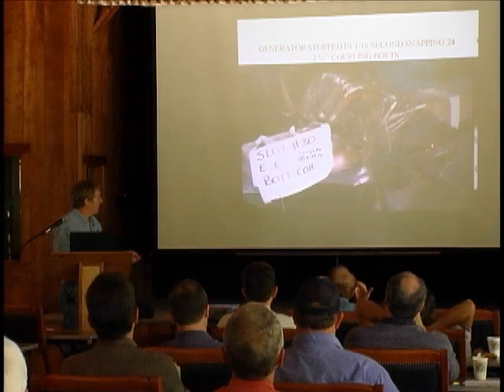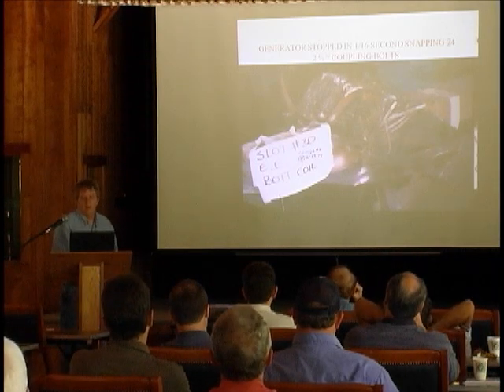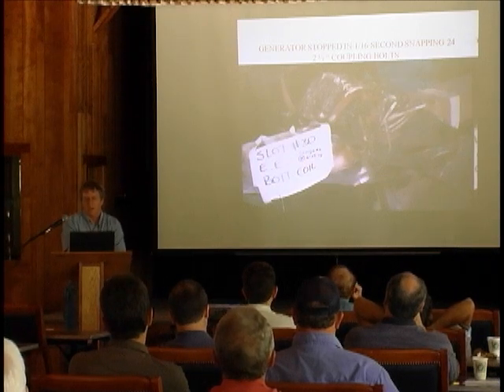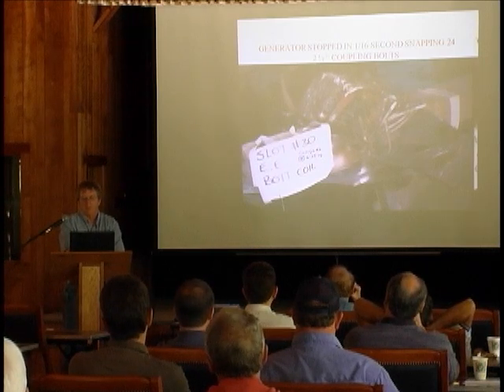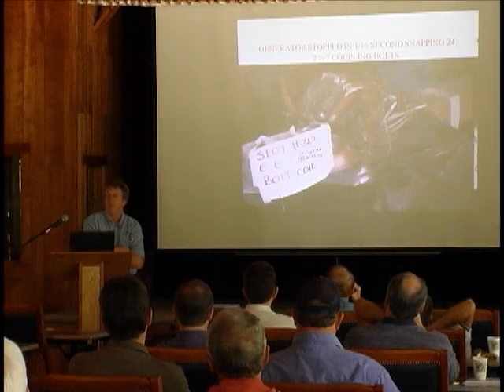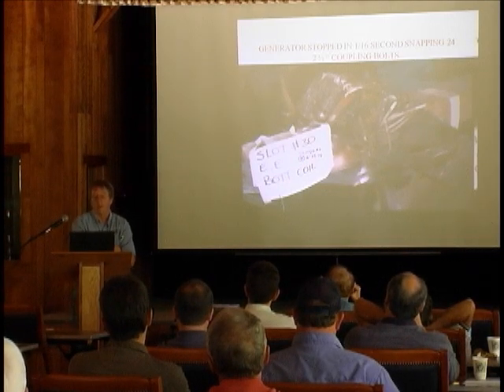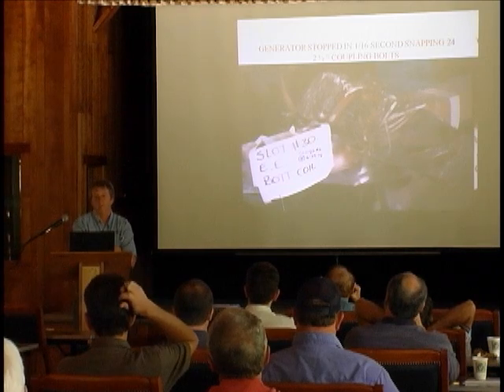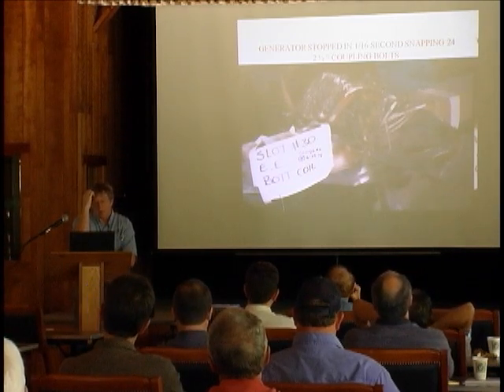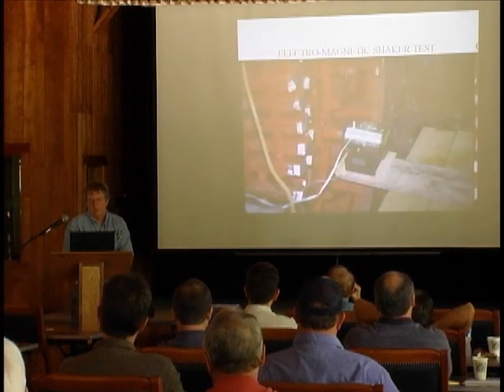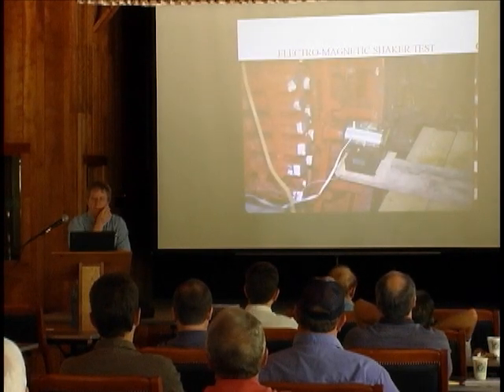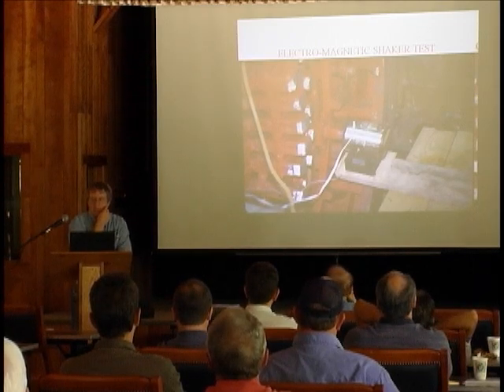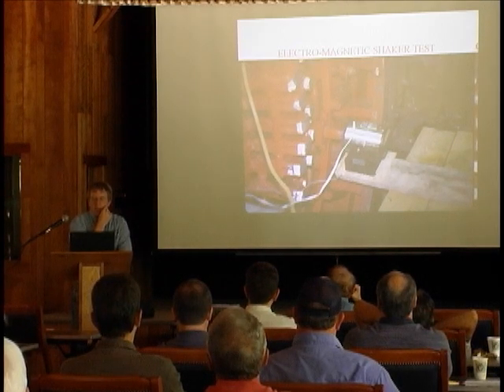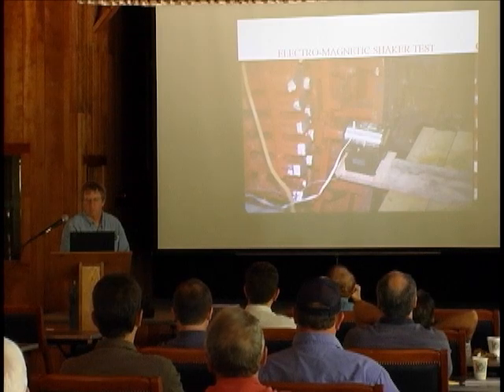And this is actually a hunk coming out of the generator. The generator had a phase-to-phase short within the generator, and the generator stopped, according to the oscillograph, in 1/16 of a second when it did this. And it had 24 2.5-inch coupling bolts that it just sheared like butter. Boom! Total lockup and a complete meltdown of the generator. And this is actually where I started. This was in '76, when I actually started doing resonance testing and things like that. And this shows a shaker on the system.